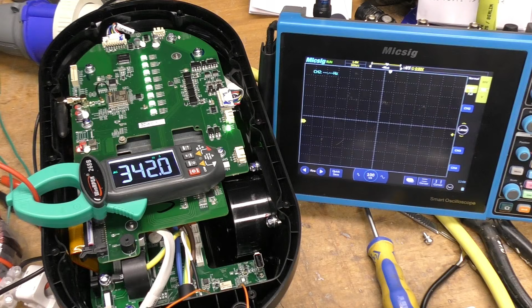Now, the PEN earth leakage detection doesn't trip on DC, but that's absolutely fine because all that's looking for is faults caused by your earth becoming live because of a PEN fault and then somebody touching the car. So that's really got nothing at all to do with the rectification going on in the car. So there's absolutely no reason why that would ever be DC. So the fact that this only trips on AC faults down the earth is entirely fine.